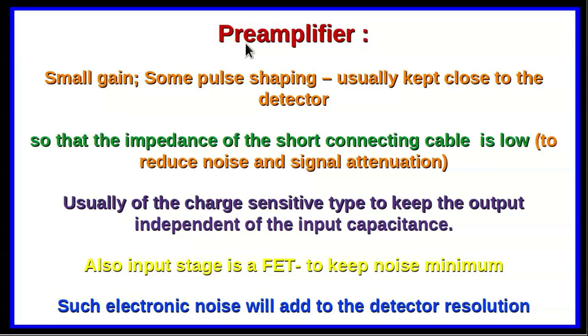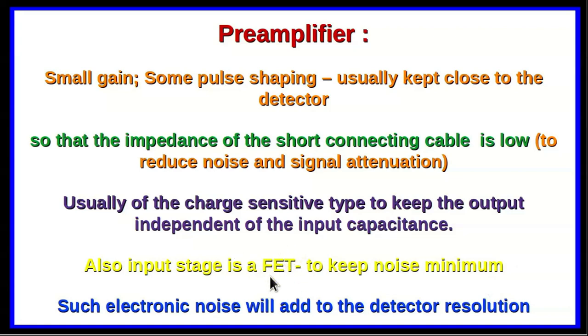The pre-amplifier normally has only a nominal gain and some pulse shaping, and is kept close to the detector. This is because the impedance of the short connecting cable will be low, reducing noise and avoiding signal attenuation. The pre-amplifier is normally of the charge-sensitive type so the output is independent of the input capacitance. To keep noise to a minimum, the input stage is a field-effect transistor (FET) stage, since electronic noise adds to the detector resolution.